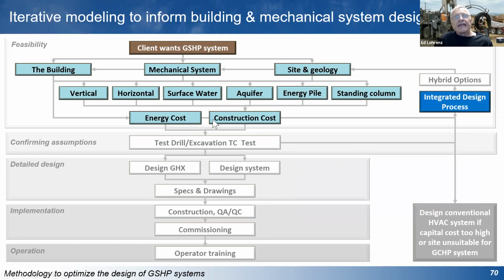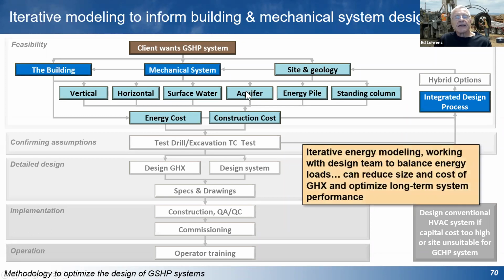And then if you can't get there with the first iteration of the energy model, if the ground heat exchanger is still too big, we'll go back to the architect, go back to the mechanical designer, look at what can be done to improve the energy balance. Look at the mechanical system again. That's where the iterative modeling comes in, in an effort to try and balance the loads.